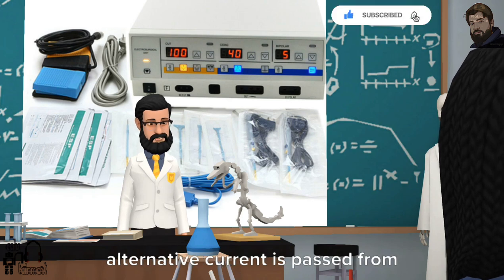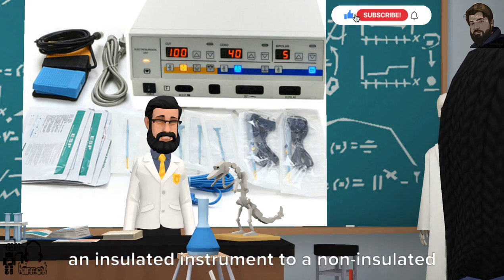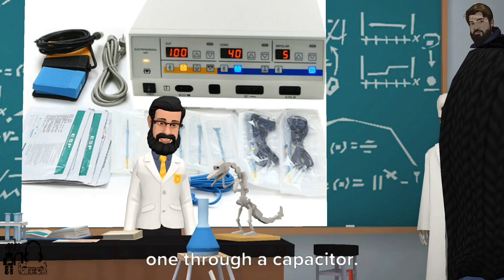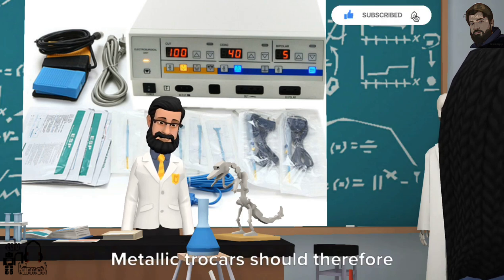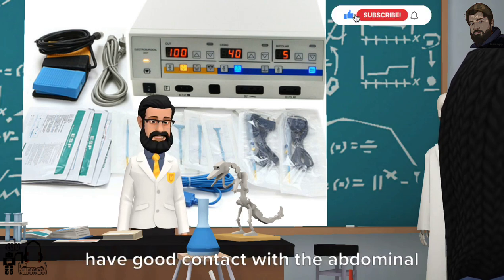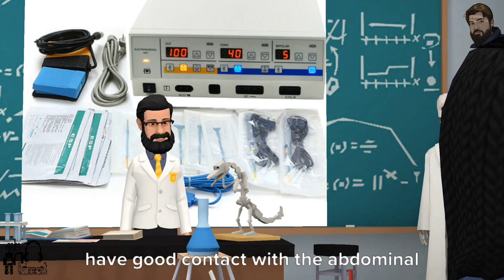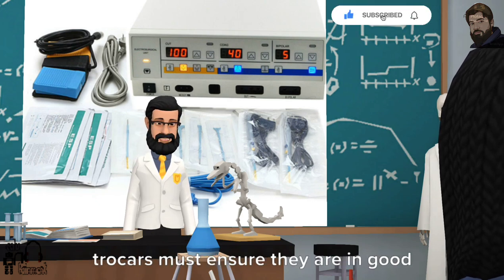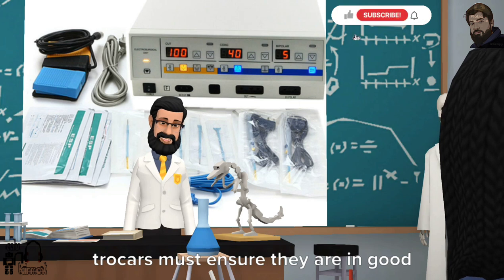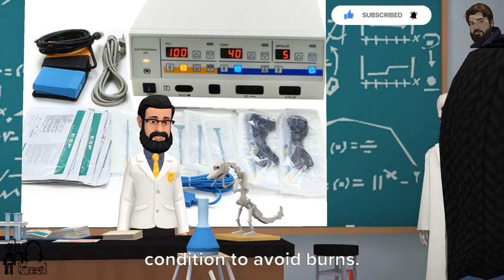Capacitive coupling can occur when alternative current is passed from an insulated instrument to an uninsulated one through a capacitor. Metallic trocars should therefore have good contact with the abdominal wall to avoid burns, and non-conducting trocars must ensure they are in good condition to avoid burns.